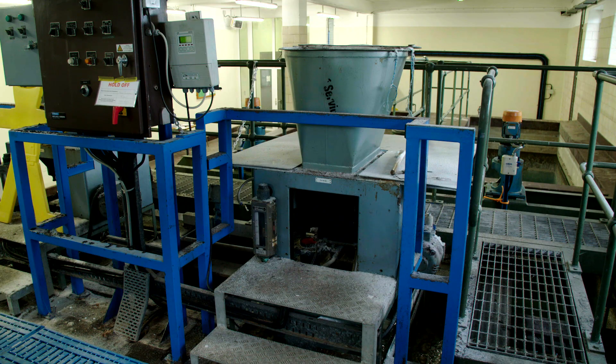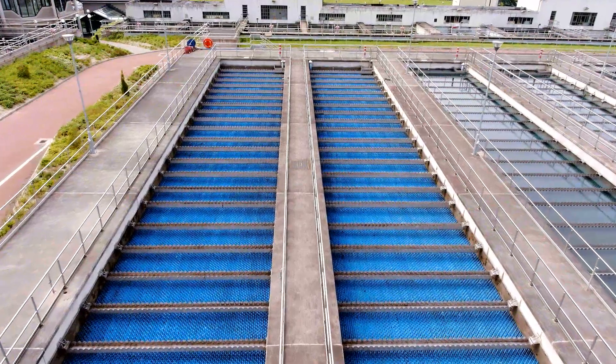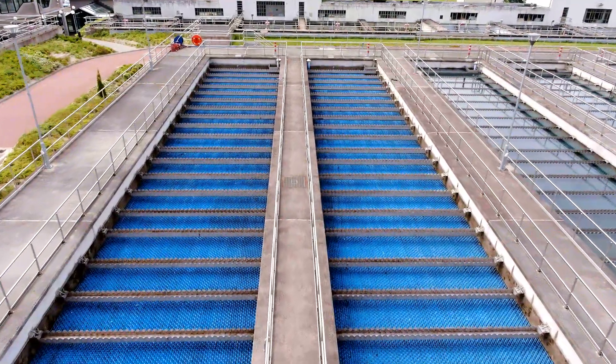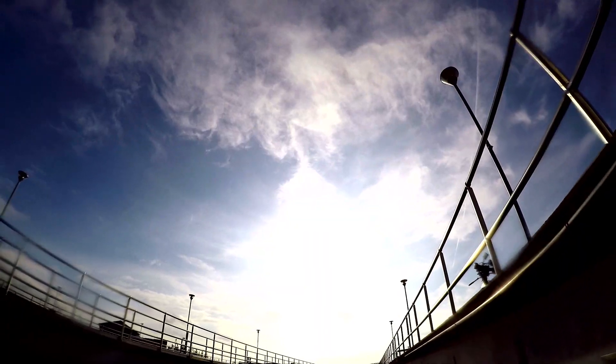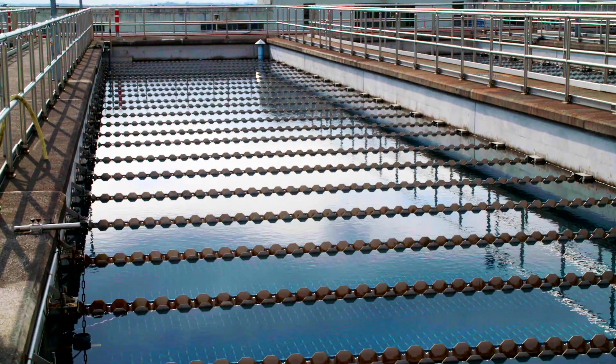First, a chemical called alum is added to the water and mixed in well. Then, the water is piped into these large settlement tanks. Here, thanks to a chemical process known as flocculation, the alum and small particles clump together to form larger particles called floc. This floc is heavy enough to sink to the bottom of the tank, where it forms a sludge.